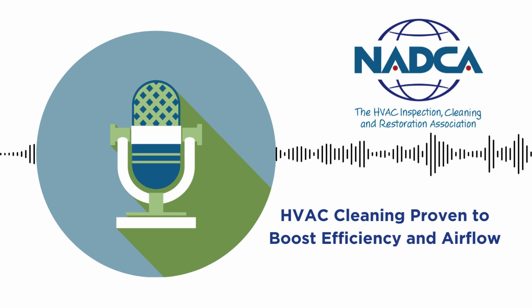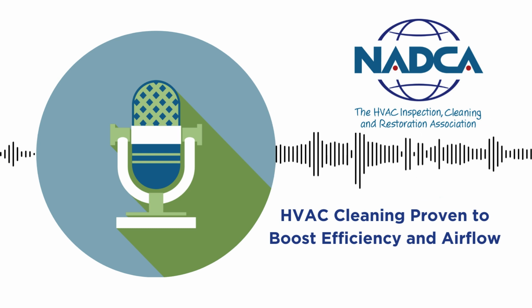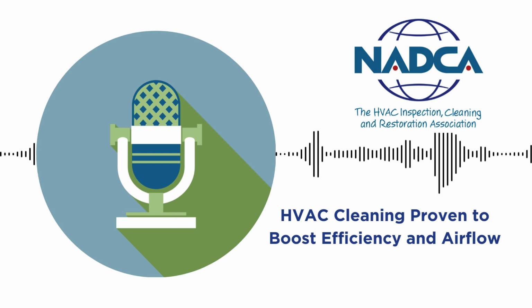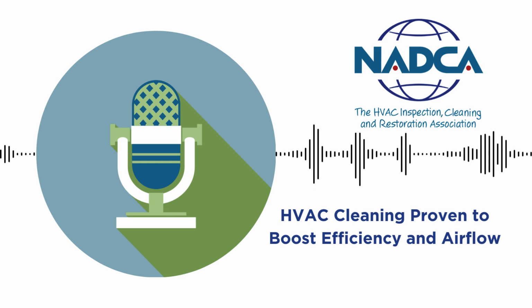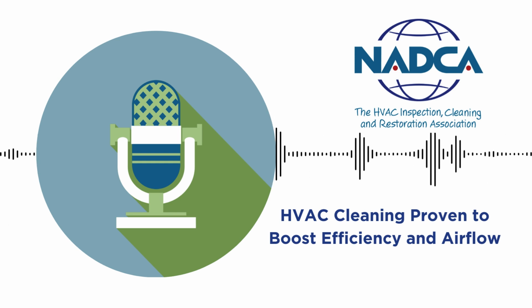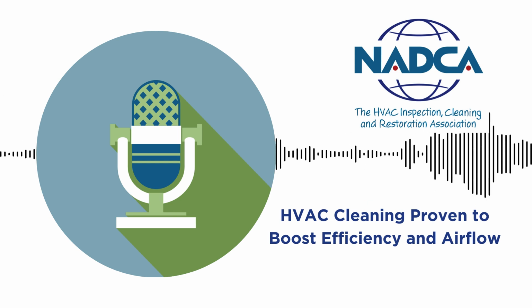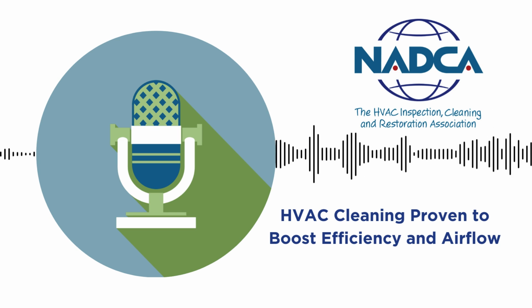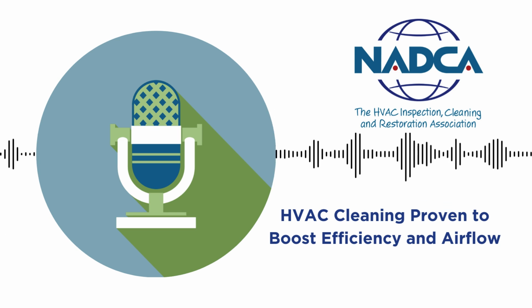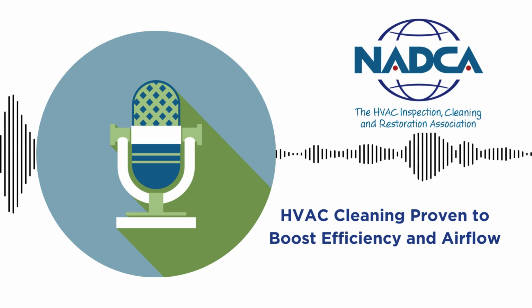All that stuff. And okay, so the article also mentions improved airflow. And I know you're big on building operations and how things actually work. Why is that so important, like the airflow? So think about it this way. When you clean the system, you're increasing the volume of conditioned air that's being delivered to the building, right? And we call that supply airflow. And that can increase by anywhere from 10 to 46% just by cleaning. So you're getting a lot more bang for your buck, essentially.